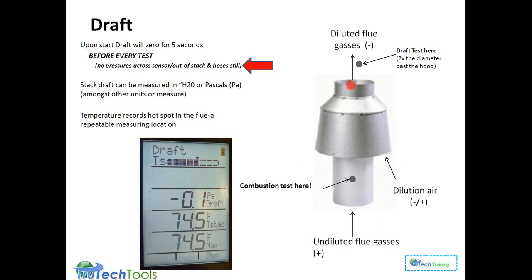However, you do want to take the draft test above where dilution air may enter the system, because that's going to be the pressure parameter that's providing the negative pressure that creates the airflow through the combustion system. So it's two important distinctions. If you have a dilution air system, you do the combustion test pre-dilution air, and you do the draft test post or after dilution air.